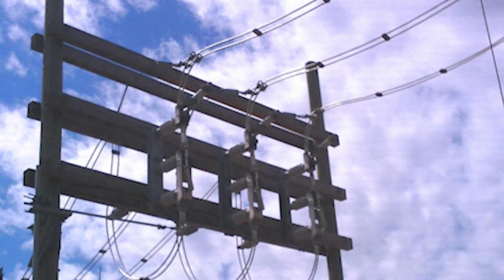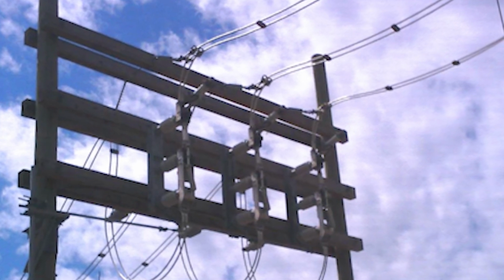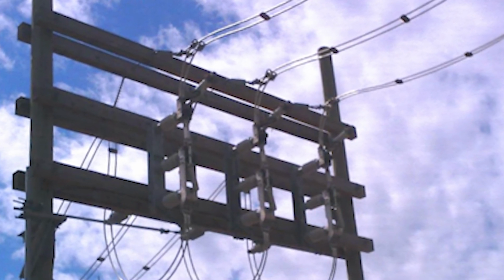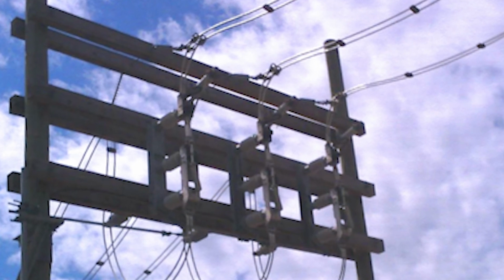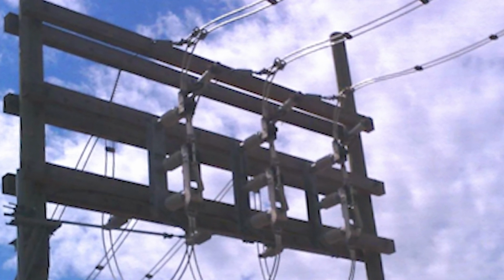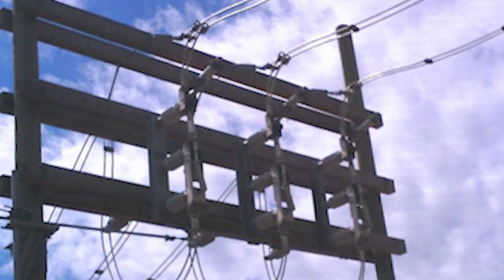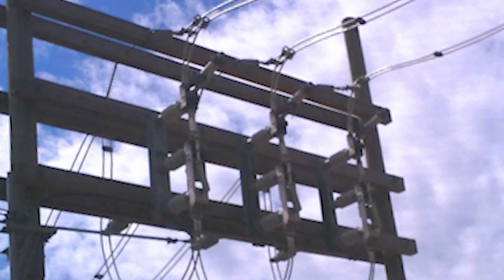You can see the 3 large cutouts with a fair bit of load on them. These conductors are about 1033 ACSR in size, and they have 2 going into each switch. At this particular time there was about 100 megawatts going through here. Everything seems to be okay in full spectrum.